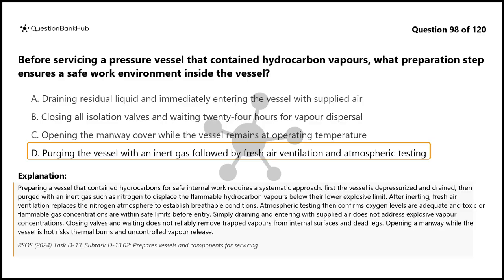Simply draining and entering with supplied air does not address explosive vapor concentrations. Closing valves and waiting does not reliably remove trapped vapors from internal surfaces and dead legs. Opening a manway while the vessel is hot risks thermal burns and uncontrolled vapor release.